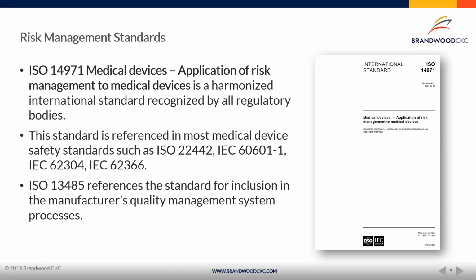So it is critical that we use this to apply to our medical device in its design and development and in the post-market activities. In addition, ISO 13485, so the regulatory requirements for medical devices, includes references to 14971 and how the manufacturer's quality management system should apply 14971 in your design and development, verification, validation, and post-market activities.